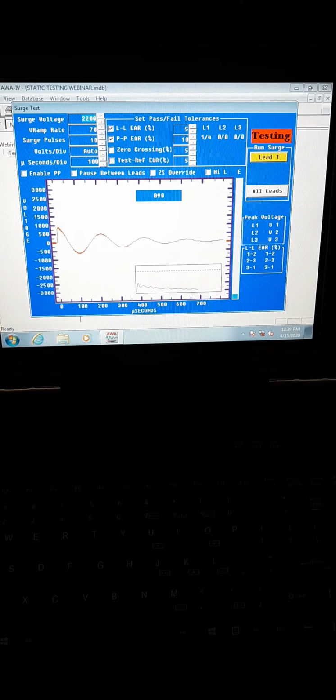Each waveform, as the voltage is being increased by 50 volt steps, or 70 volt steps in this case, each pulse has a waveform, and we're comparing the difference between the waveforms or the pulses as that voltage is being increased in equal steps. So what we're looking for are spikes in the pulse-to-pulse graph that would indicate a sudden large change from one pulse to the other. In other words, a large difference between the waveforms from those two pulses.